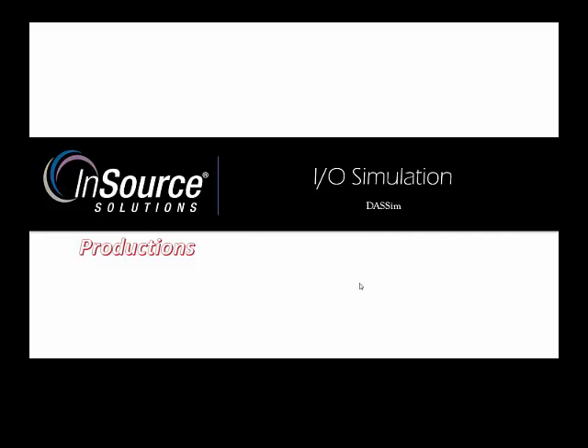We're going to choose some algorithms that we want to generate some data, whether it's a sine wave or a sawtooth. We can generate some toggle bits going on and off, and we can change the frequency and things like that. So it's a nice little tool to test your systems, test your objects, test your tags, test your graphics, test data going to your historian. Anything you can do with a real live process, we can simulate with this tool and bring data in.